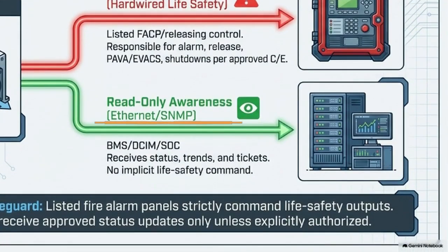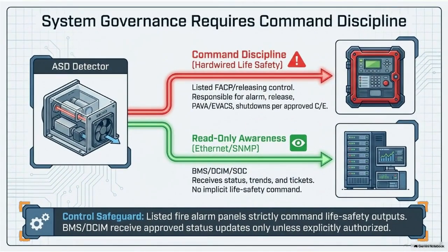Alarm, release, evacuation, and shutdown sequences must be executed exclusively by a hardwired, listed fire alarm control panel. The bottom path is read-only awareness. The Building Management System and DCIM receive status updates, trends, and trouble tickets via Ethernet, providing situational awareness to the IT team. The control safeguard here is absolute. Commercial software platforms cannot hold any implicit life safety command authority.